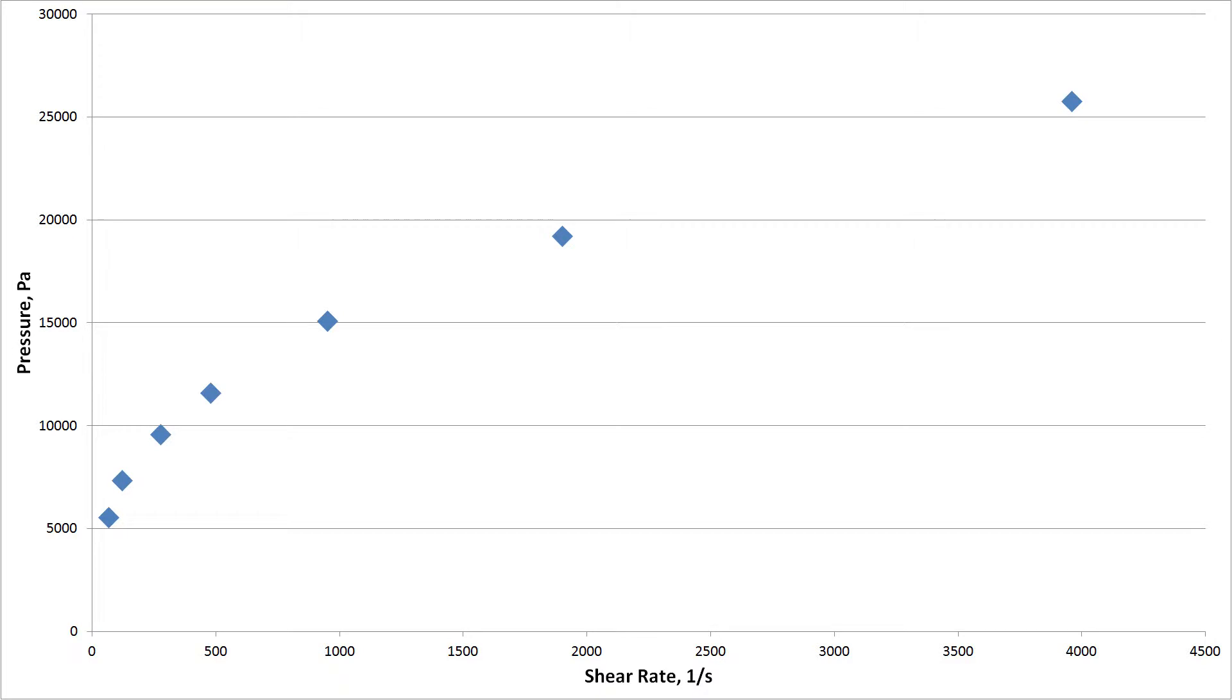Shear thinning samples, in essence, extend the available shear rate range because your pressure no longer increases in direct correlation to shear rate.